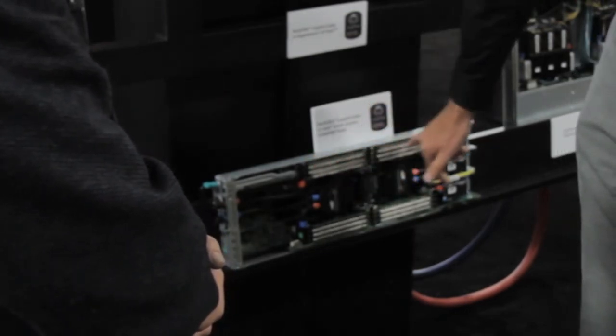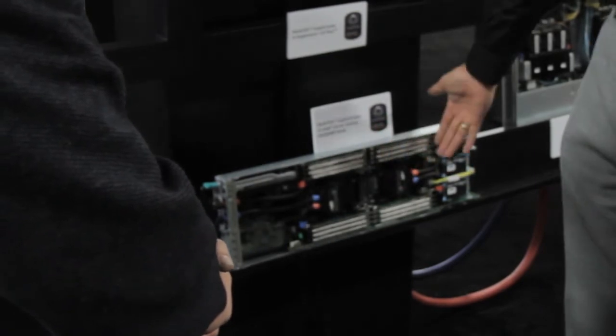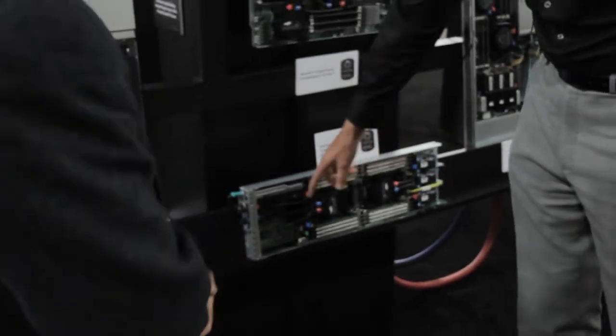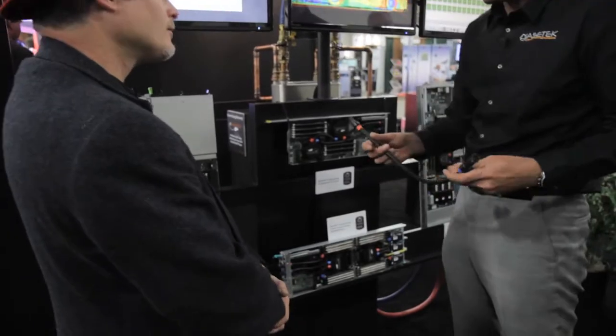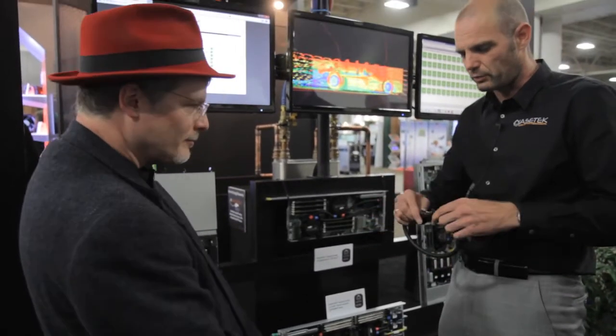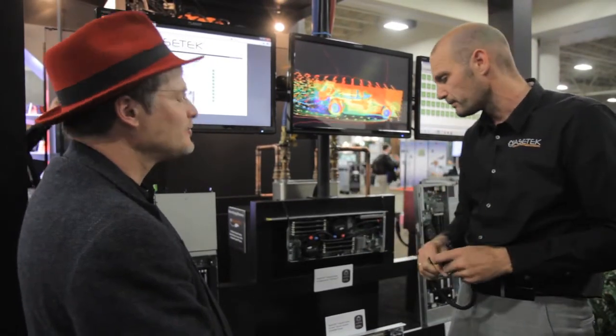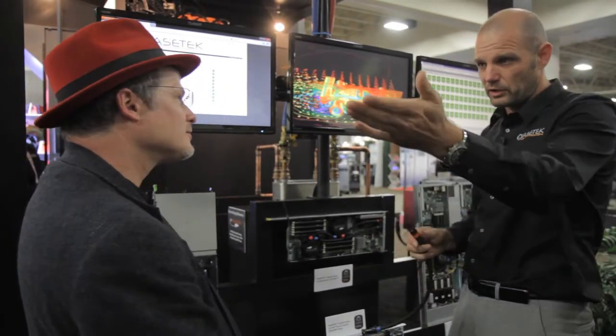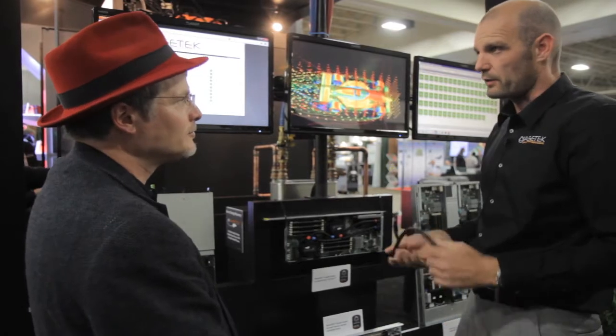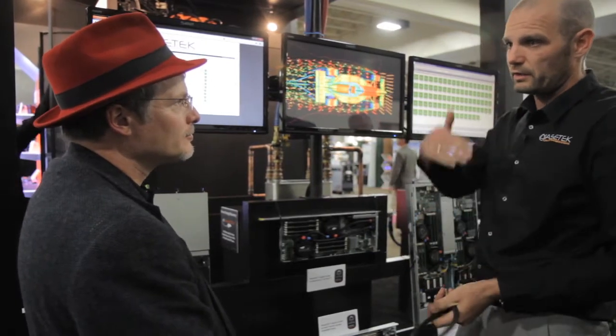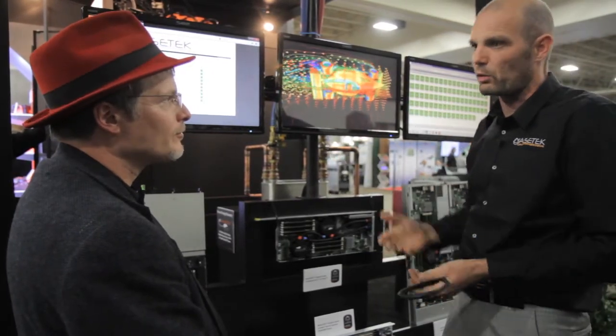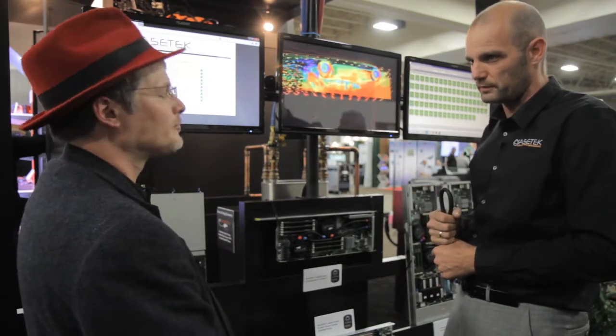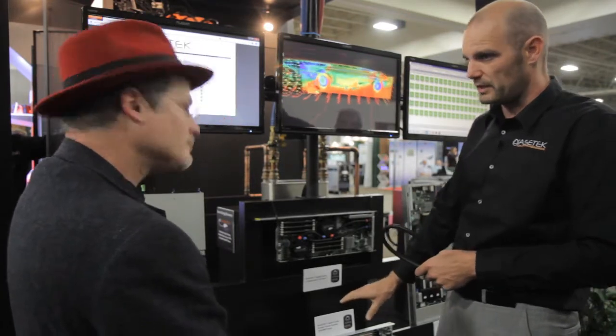Between the memory DIMMs we also have coolers. All that heat gets pumped out of the server through tubes with dripless quick connects, there's fluid inside this tube right now. That connects into a rack CDU behind you, which transports the liquid out of the system into the facility's water or up onto the dry cooler. There are 92 of these nodes.